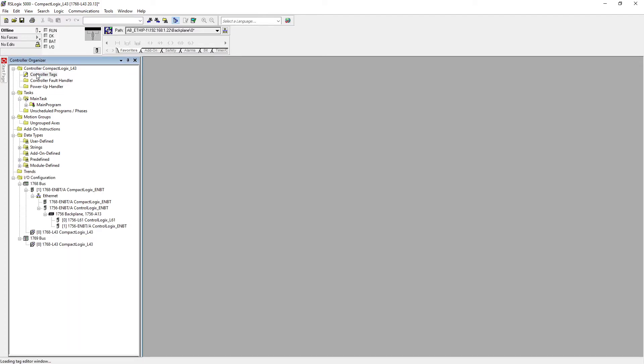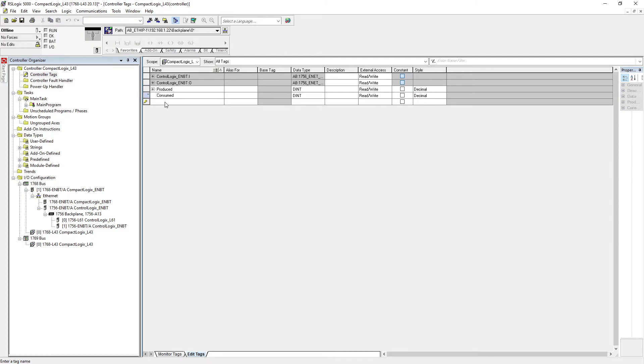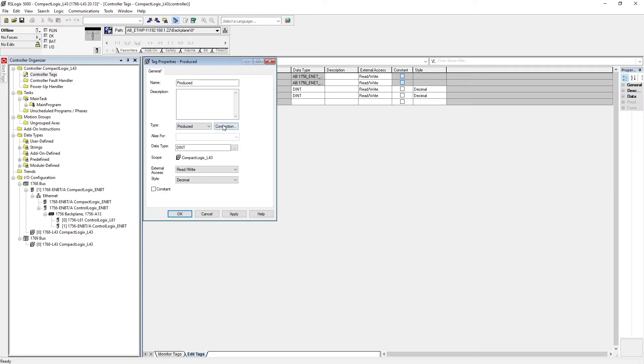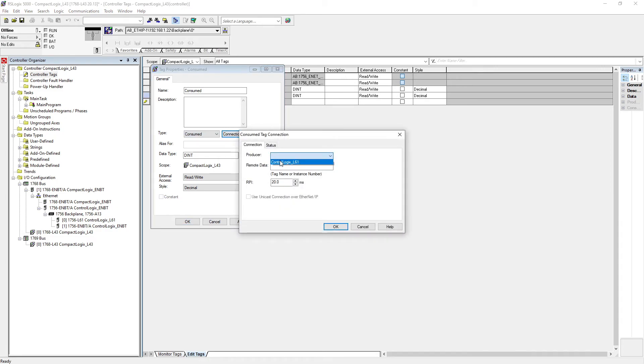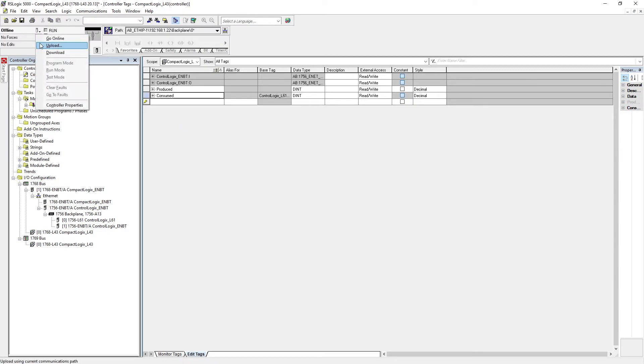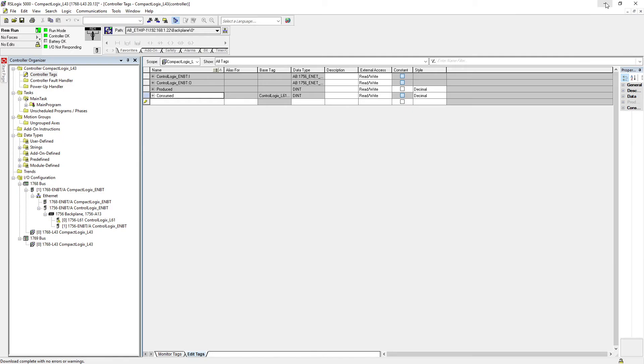Now we can go offline — we're going to create our produce and consume tags. In the controller tags it's going to be 'produced' and 'consumed.' On the produce tag, when we go to properties we're going to select 'Produced,' go to connection — looks good, hit OK, apply, OK. On the consume side, when you select 'Consumed' and go to connection, you need to select the L61 and where you are pulling the data from. So in our other PLC we're going to create the same tag name — 'produced.' That's where we want to pull the data from. Hit OK, apply, OK. Then just hit download.